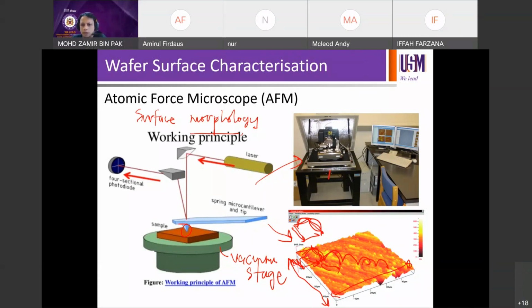Besides, another parameter that you usually set will be the resolution of the scan. Resolution. It's not here on this page, but I'll just write it down. So resolution is how small do you want to go between points. Okay, for example, if you scan 50 by 50 micron, in this case, if you go 50 by 50, just like what you have on this image, 512 pixels, dia ada beberapa setting. Usually we use 256 pixel, 512 pixel. So 256 resolution or 512 resolution, sama, pixel size atau resolution is actually referring to the same thing. So if you're scanning 256, if you're using 256 pixels of resolution on this particular field size, so that means you will have 256 points throughout your axis. Katalah you scan 50 by 50, okay? Then you're gonna have along this axis, you're gonna have 256 point.